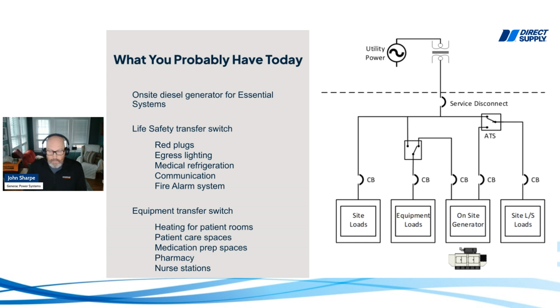So what is a solution that's got to be had? Well, the simplest solution, if you're fortunate, is that we take the site HVAC loads, the heating, ventilating, air conditioning loads, and tie those to the output of the equipment transfer switch. So you separate those air conditioning loads and tie them to the equipment loads.